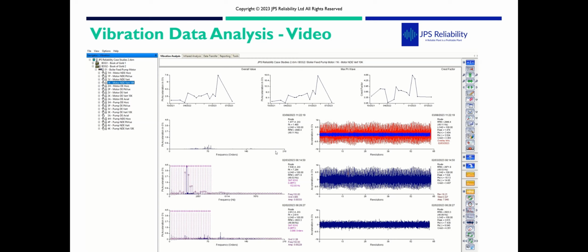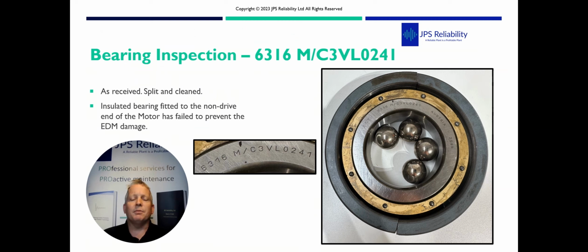Okay, what we're going to do now is jump in to look at some of the bearing photos. So this is the bearing when we received it after overhaul. You'll see it's a 6316. You'll see the long code at the end to indicate it's an Insocoat bearing, and you can actually see the grey coat on the bearing. So this was fitted to the non-drive end of the motor, and it failed due to EDM damage.